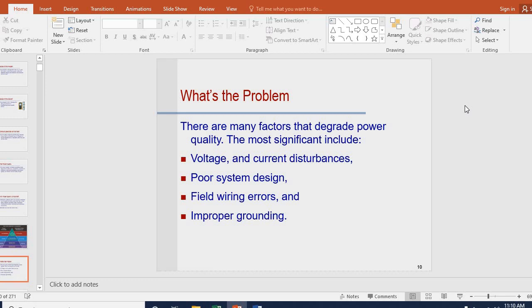Let's see. There are many factors that degrade power quality. The most significant includes voltage and current disturbances, poor system design, field wiring errors, and improper grounding. Never thought really on the neutrals and the grounding being such a problem until later on in my career, and it is really important.